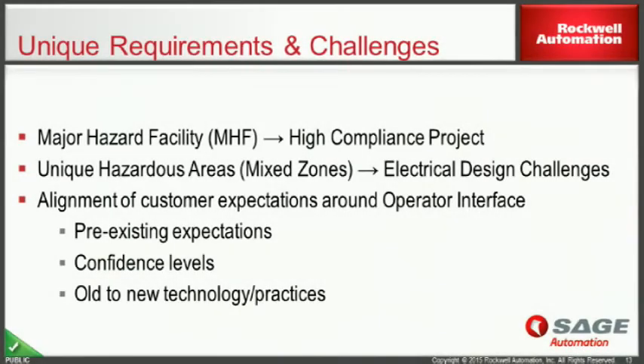So some of our unique requirements and challenges. It's a major hazard facility, this particular one, so that equates to a high compliance project. A lot of hoops to jump through, real focus on validation of old for new functionality. A lot of unique hazardous areas, a lot of mixed zones, not only vapour, not only dust, combination of all, and that equated to quite some challenging electrical design aspects for the equipment that we actually replaced within the process buildings.